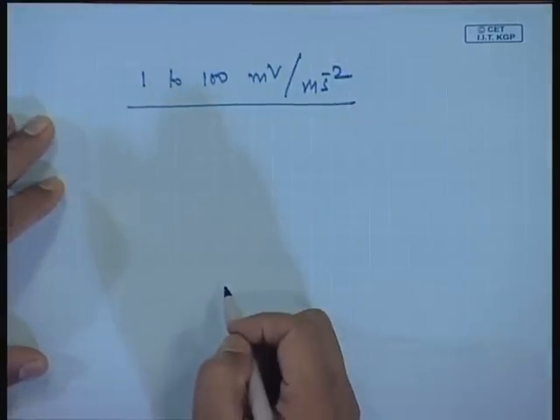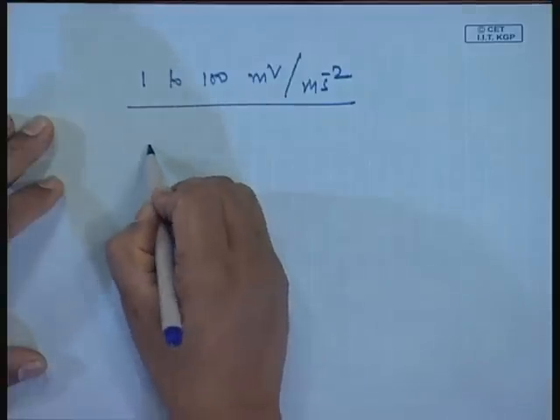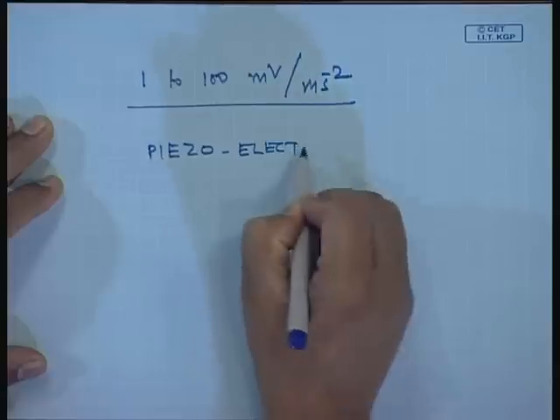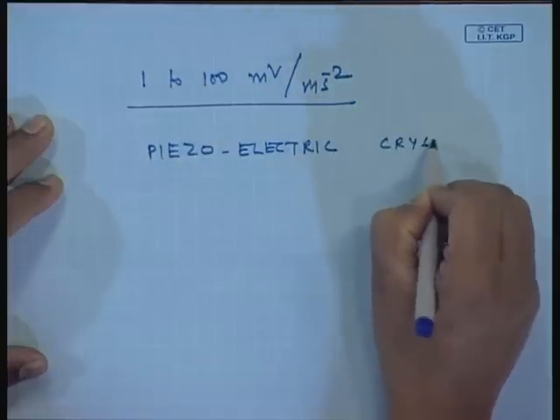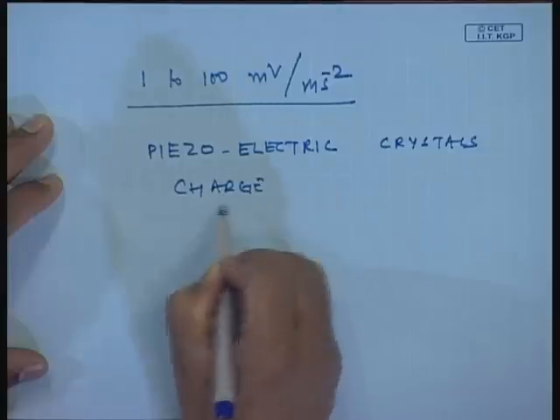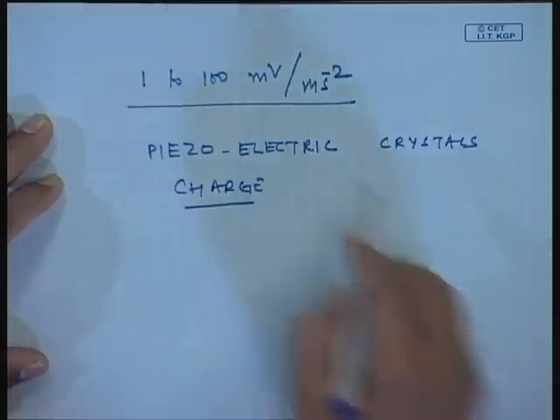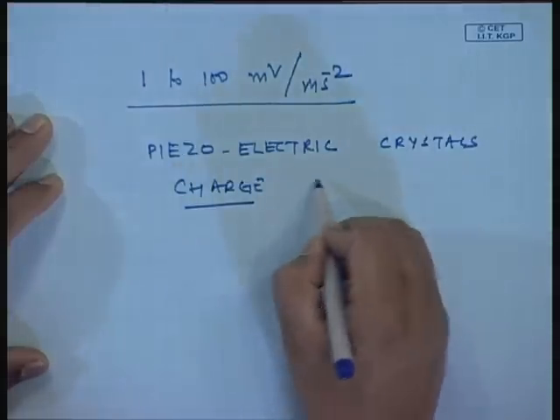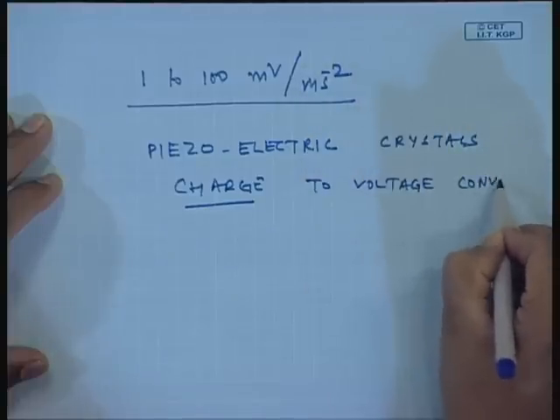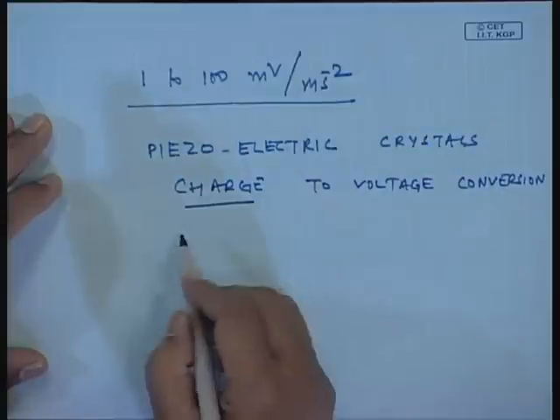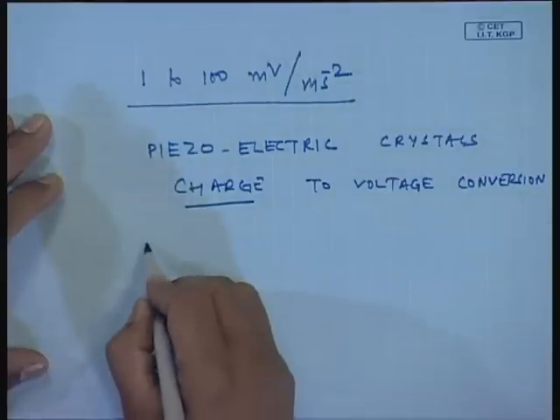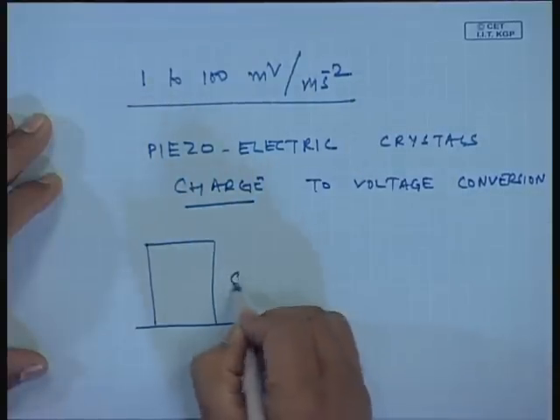The piezoelectric crystals produce a charge. I cannot store the charge for a long time because it will discharge and decay with time. So a charge-to-voltage conversion needs to be done, and once I have the voltage I can send it through the signal chain. Some accelerometers are the charge type - the output from this is a charge.